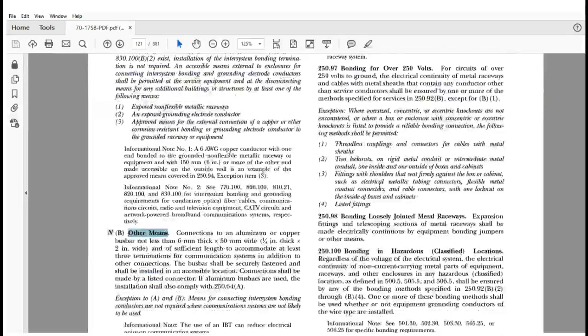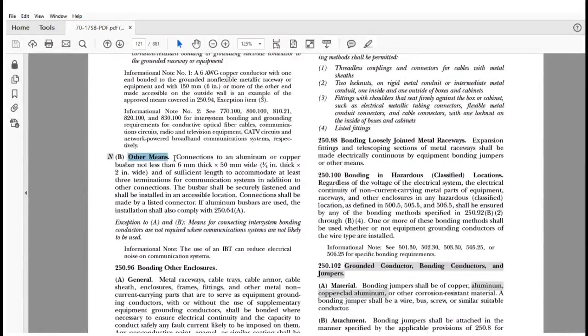But if you want to do that, under the other means, it says, all right, here's your other option. If you want to take an aluminum or copper bus bar that is not less than 1/4 inch thick, which is very familiar terminology, and 2 inches wide, and just like always when this provision comes in here, that it has sufficient length to accommodate at least 3 terminations for communication systems, in addition to other connections, the bus bar shall be securely fastened and shall be installed in an accessible location.